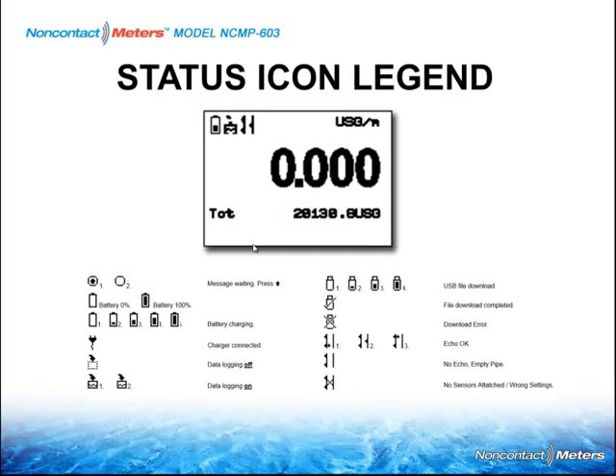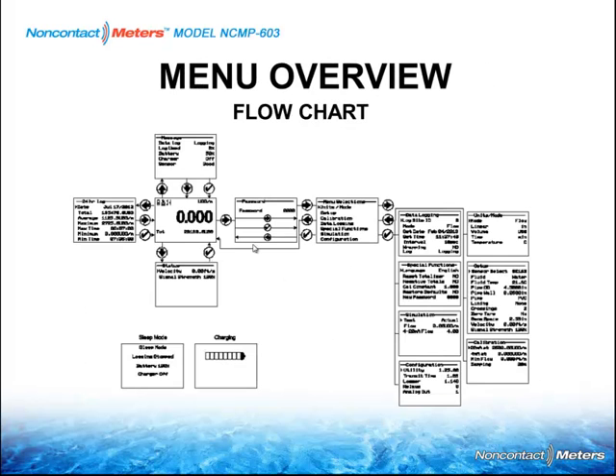The device has a lot of very interesting status icons, and we'll tiptoe through a few of these. It will show you the battery performance, whether the logger is on or off, and your USB file status. It'll also show you if the echoes are acceptable based upon the recommended crossings, tell you about an empty pipe or no echo symbol, and tell you when no sensors are attached. So it's a very informative device without reading the manual.